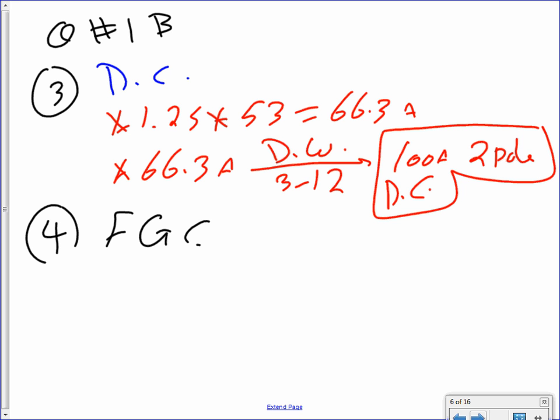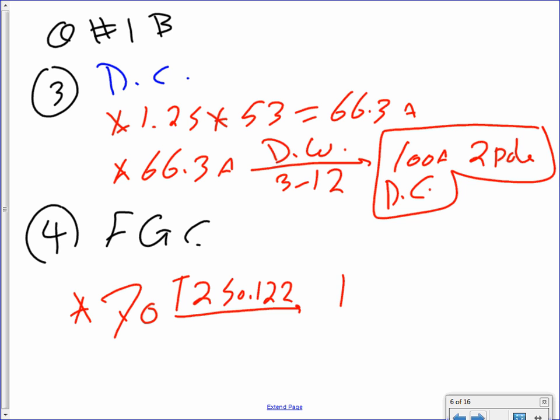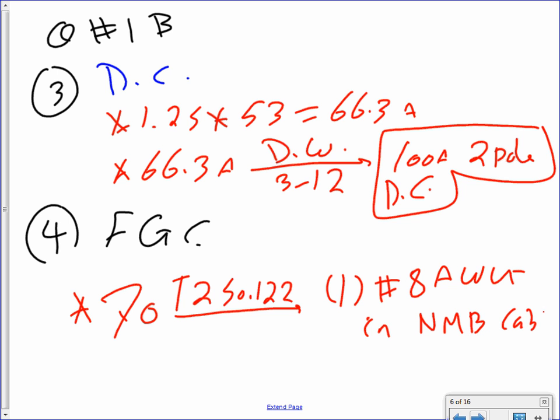Equipment grounding conductor, guys. Piece of cake. You take the 70 amp, because the circuit breaker is 70 amp. Take this one to 250.122, and that'll get you one conductor number 8 AWG in an NM cable.